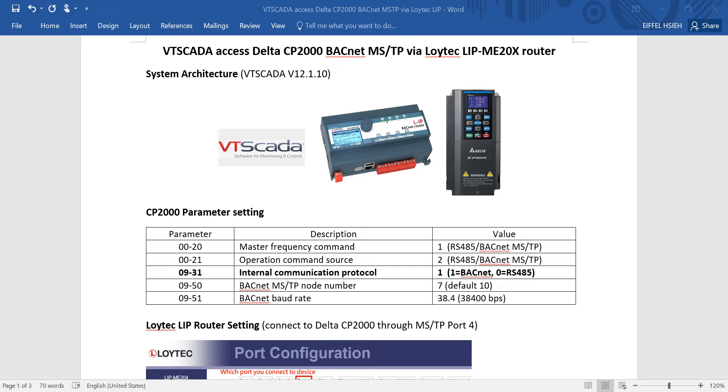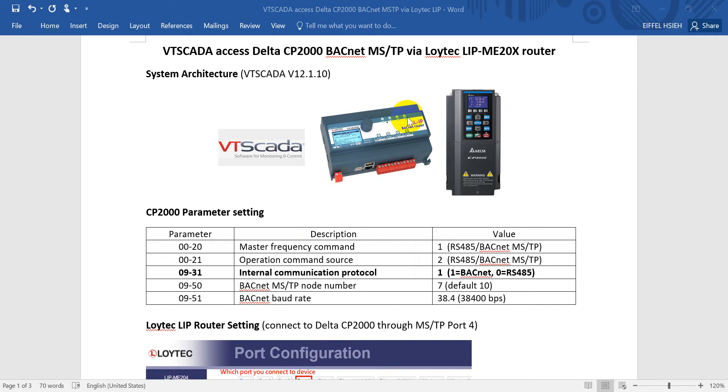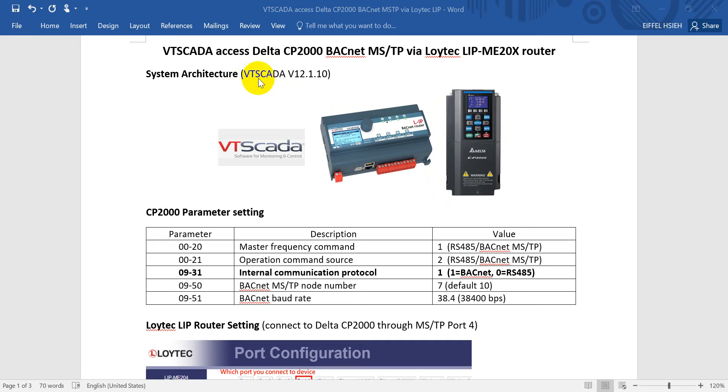Hi everyone, this topic will talk about VT SCADA accessing Delta CP2000 BACnet MSTP via Loytec LIP ME20X router. For the system architecture, you can see we'll use VT SCADA connected to the Ethernet port of Loytec BACnet IP router. Then we use the MSTP port to connect to the CP2000. Today's example uses VT SCADA version 12.1.10.